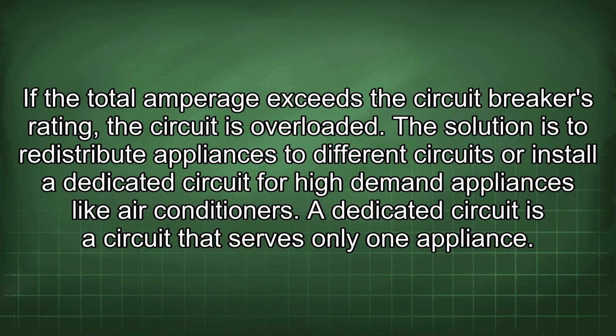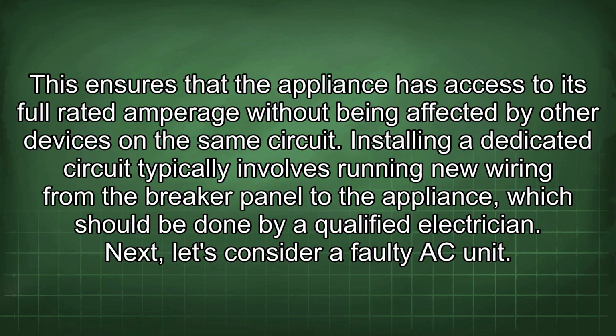The solution is to redistribute appliances to different circuits or install a dedicated circuit for high-demand appliances like air conditioners. A dedicated circuit is a circuit that serves only one appliance. This ensures that the appliance has access to its full rated amperage without being affected by other devices on the same circuit. Installing a dedicated circuit typically involves running new wiring from the breaker panel to the appliance, which should be done by a qualified electrician.